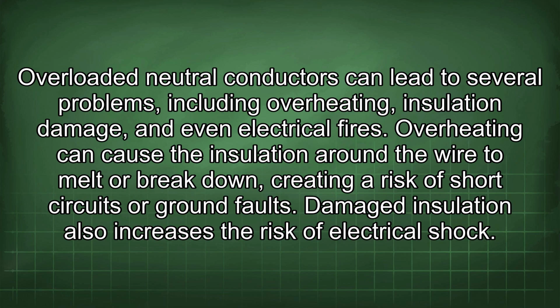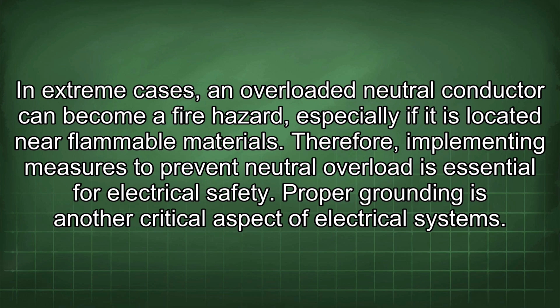Overheating can cause the insulation around the wire to melt or break down, creating a risk of short circuits or ground faults. Damaged insulation also increases the risk of electrical shock. In extreme cases, an overloaded neutral conductor can become a fire hazard, especially if it is located near flammable materials. Therefore, implementing measures to prevent neutral overload is essential for electrical safety.